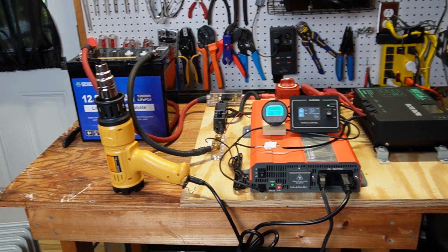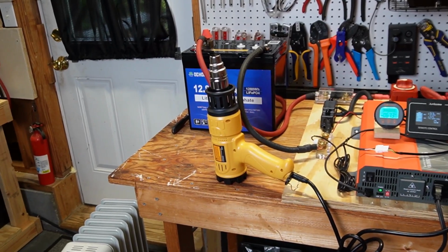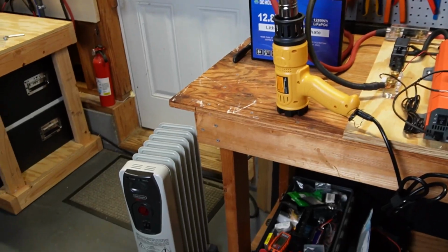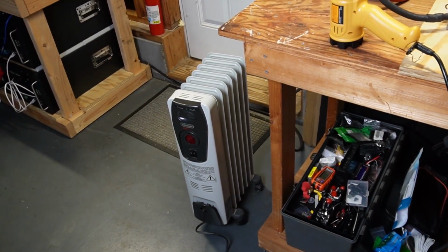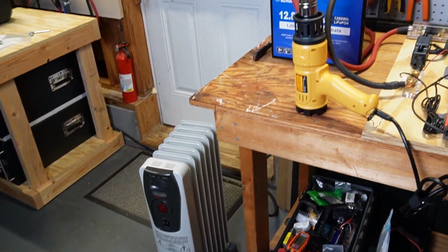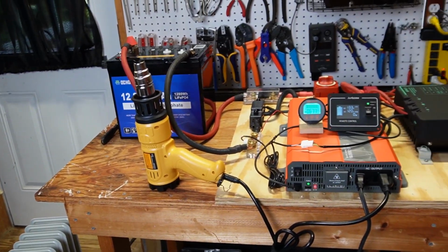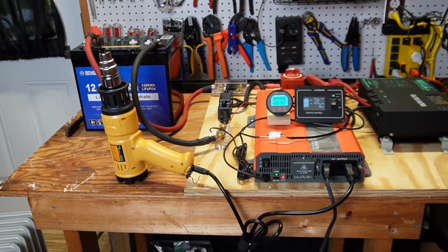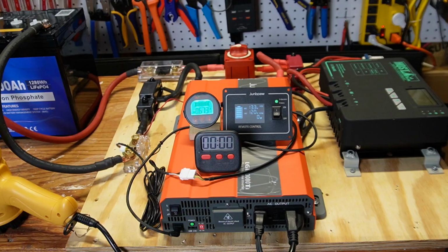To do this test I have a heat gun, which I can dial the amps in pretty well, and this oil heater on the floor here. I'm only going to turn one of the burners on, plus this, and try to get just a little over 100 amps.